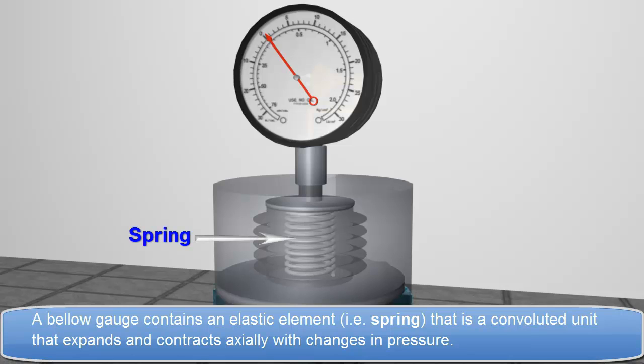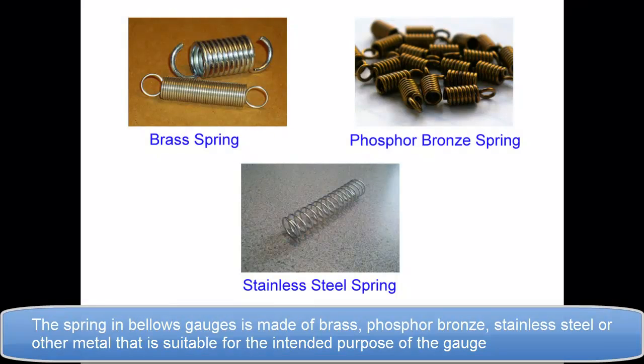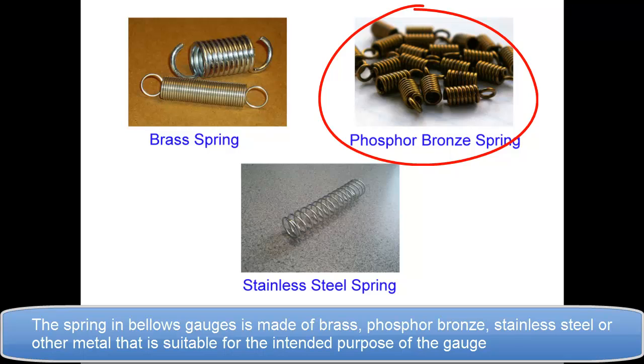that is a convoluted unit that expands and contracts axially with changes in pressure. The spring in bellows gauges is made of brass, phosphor bronze, stainless steel or other metal that is suitable for the intended purpose of the gauge.